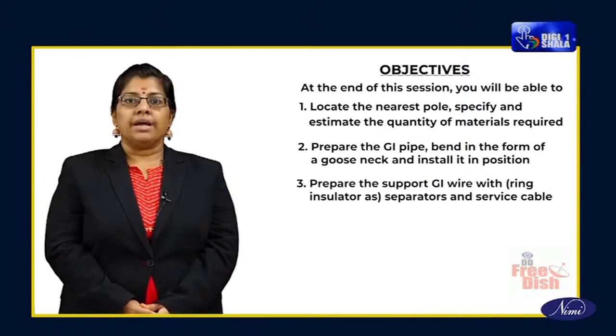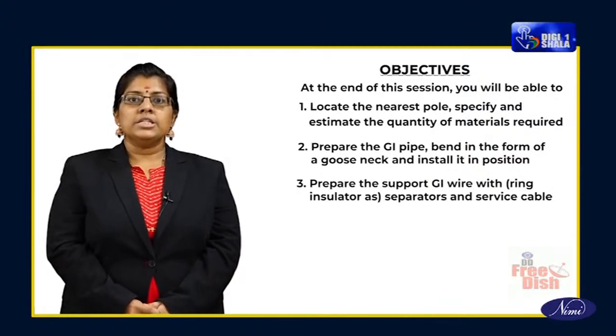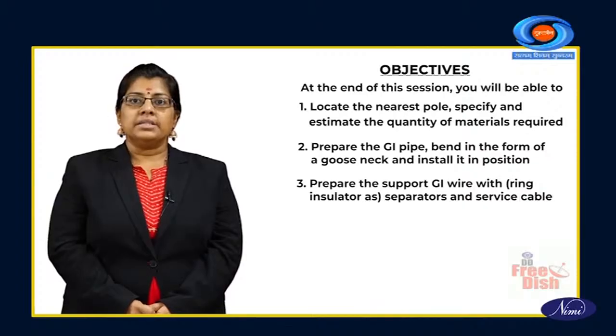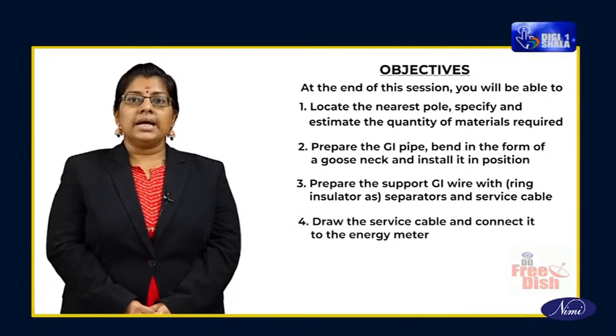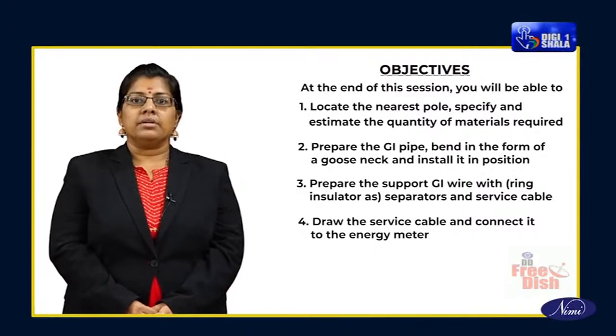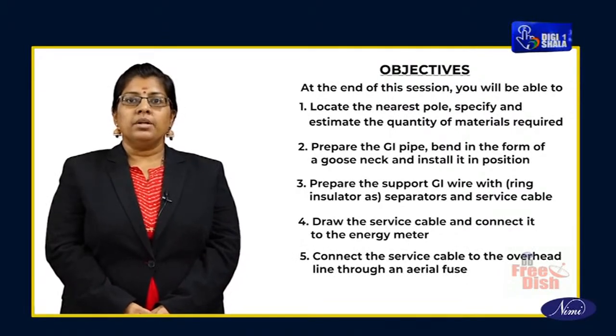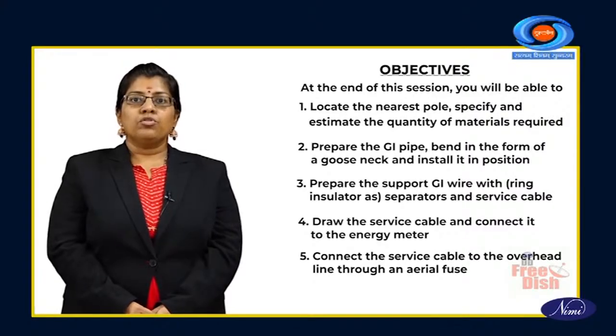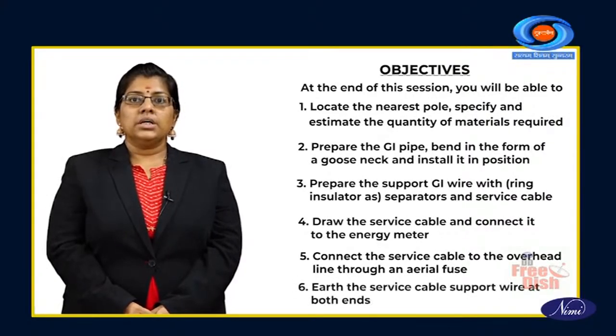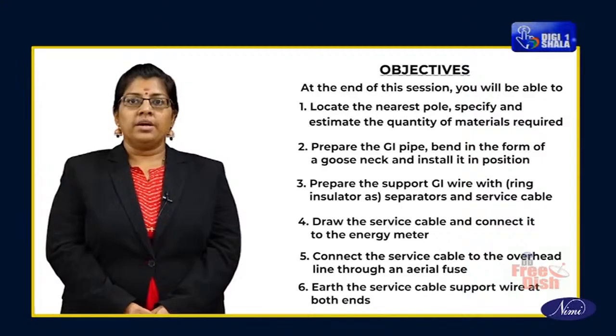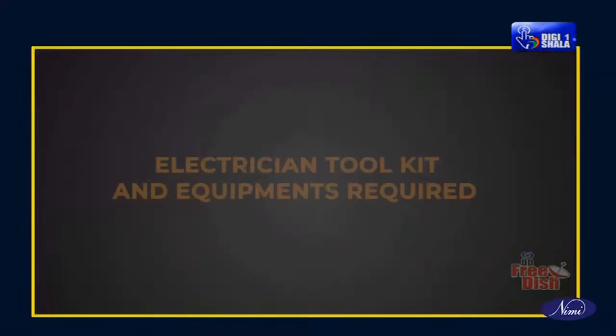Prepare the support GI wire with ring insulator as separators and service cable. Draw the service cable and connect it to the energy meter. Connect the service cable to the overhead line through an aerial fuse. Earth the service cable support wire at both ends.